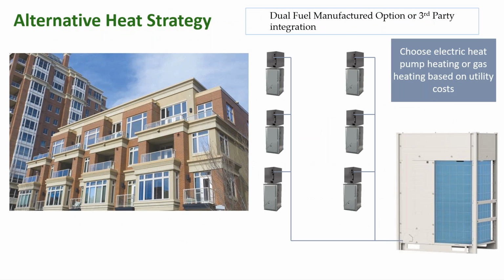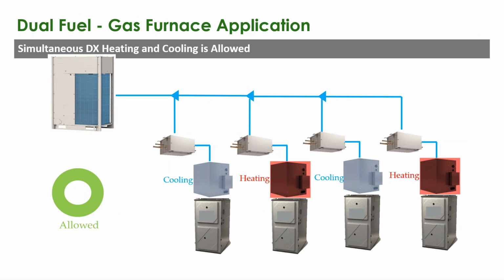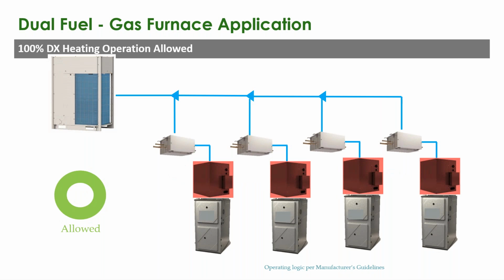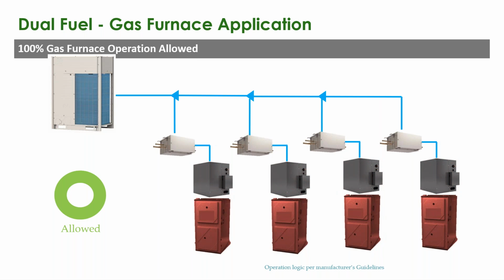One of the other strategies out there is doing a dual fuel setup, either a manufactured option or through a third-party integration that most manufacturers have an option for now. This allows you to choose where your changeover point is easily through the system logic, changing from heat pump heating to gas heating based off of temperature and utility cost benefit. This is great for multifamily central systems that are covering multiple rooms. It still allows you to operate DX cooling and heating simultaneously when you're on the DX side of things. You can also run 100% DX heating operation as allowed down into that balance point. And once you get to that balance point, everything switches over to gas heat.